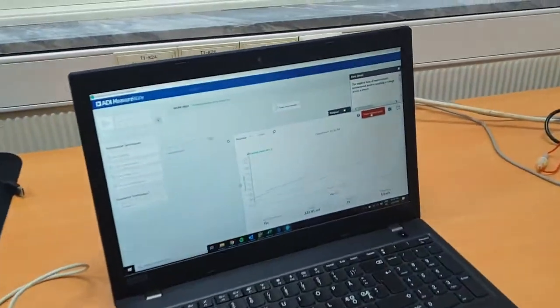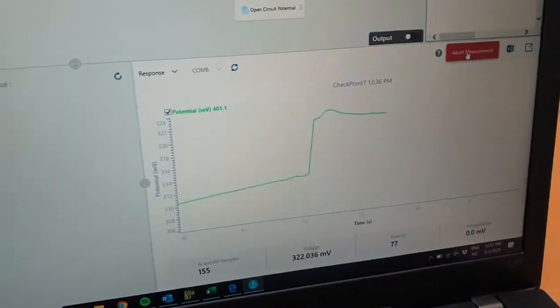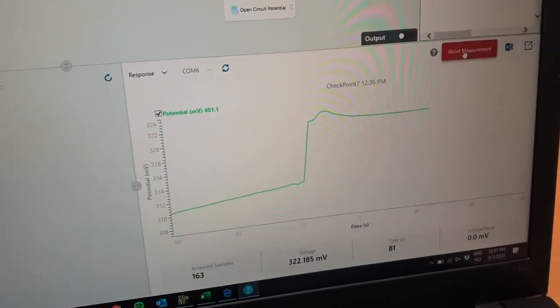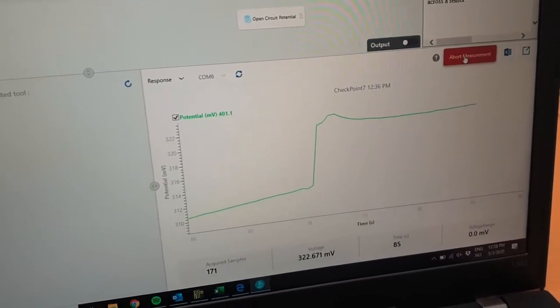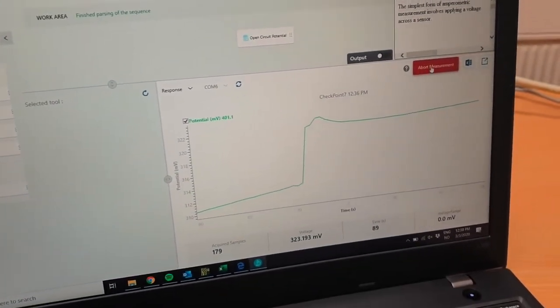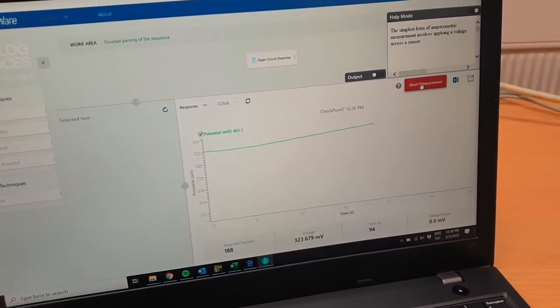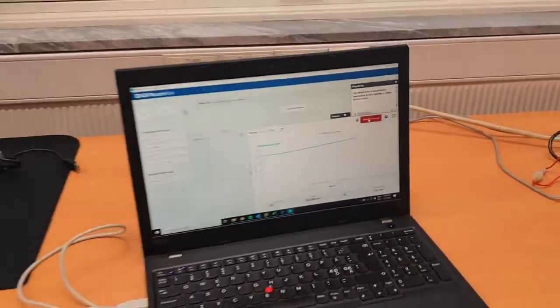So then if you zoom in on that, you can see that we've changed the voltage, and the reason the voltage has changed is because of the pH. So as long as we do a calibration of our sensor, or we know the calibration factors, we can turn that voltage back into a pH. So let me summarize what we did.